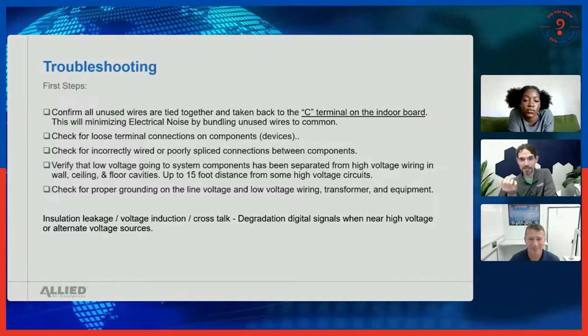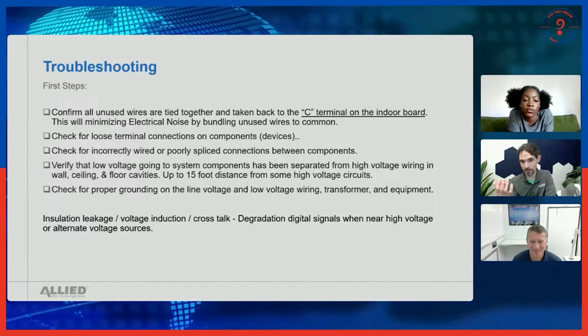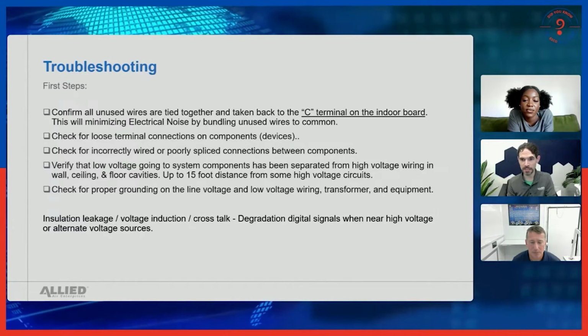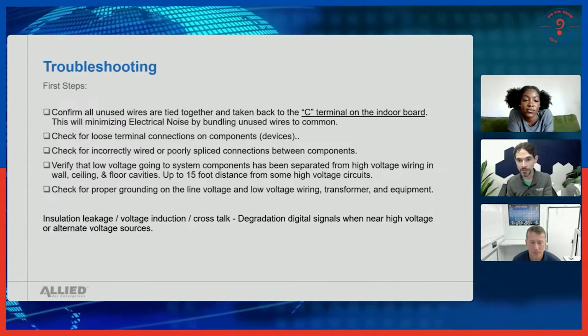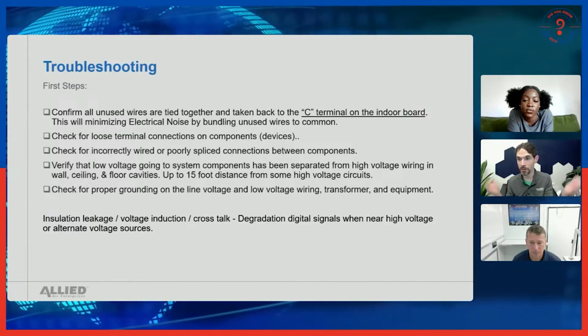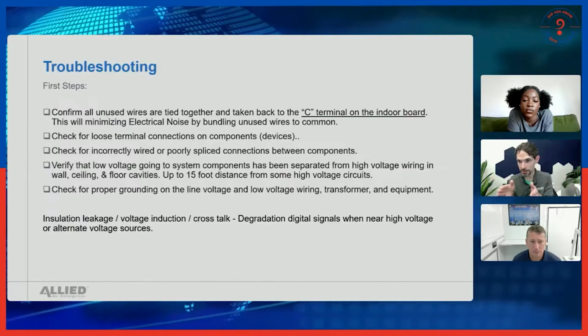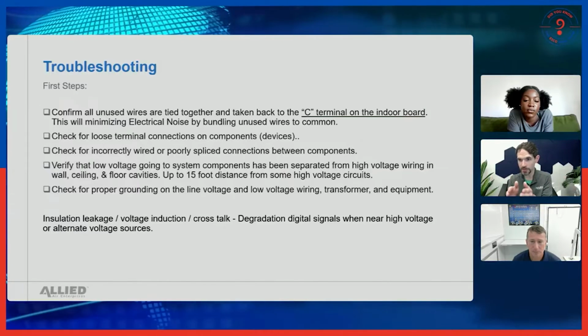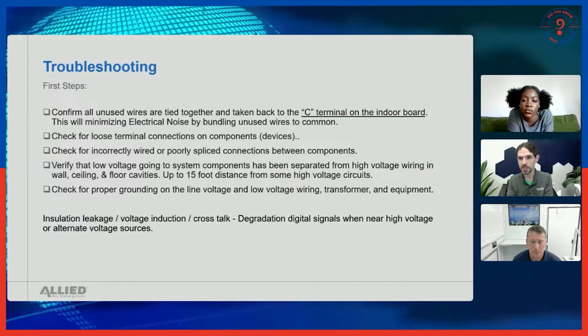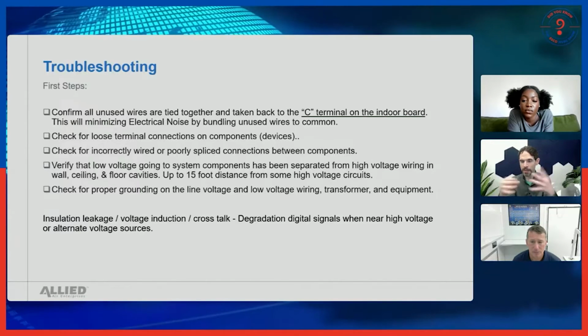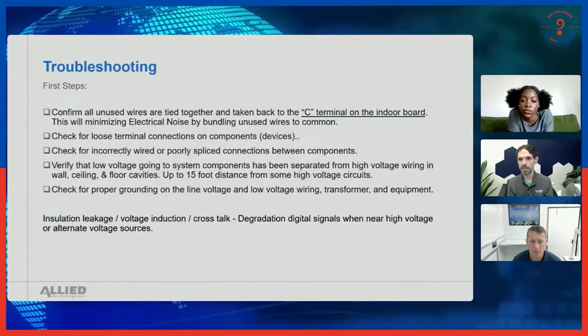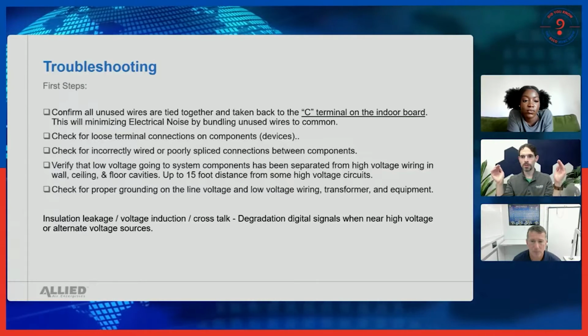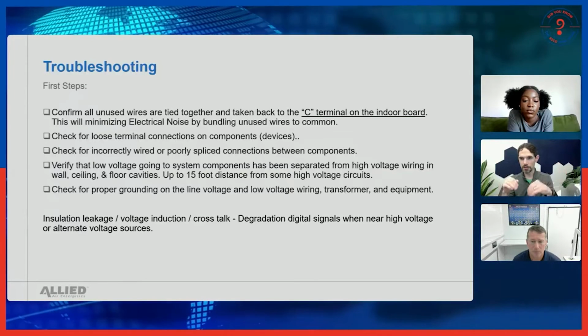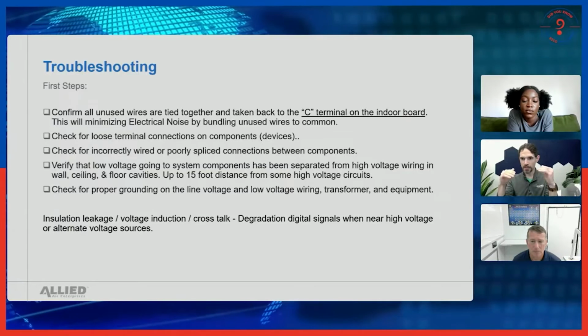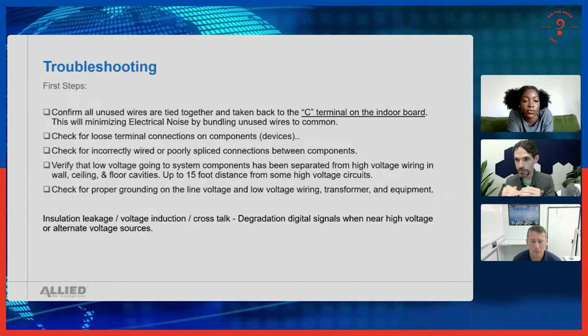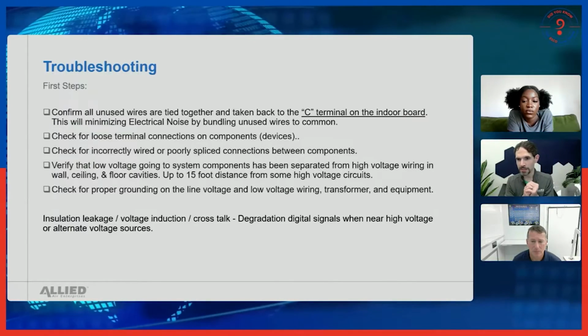And the insulation on the wire, is there insulation leakage, induction from a higher voltage, like we talked about, crosstalk between similarly run wires in close proximity doing communication? All of that comes down to whether we're somehow disrupting, degrading, or distorting the lower voltage, the little guy.